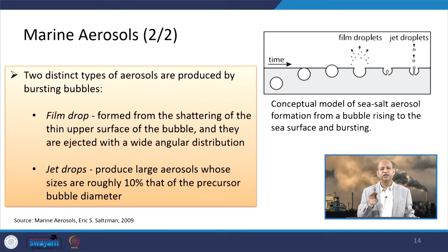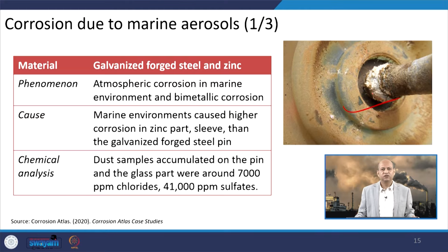As you can see, this is atmospheric corrosion in a marine environment, and bimetallic corrosion happens, you can see in the figure also. So, marine environments caused higher corrosion in the zinc part or these sleeve related parts than the galvanized forged steel pin, you can see here. So, that corrosion is because of this marine environment emitting aerosols. Okay. Then dust samples accumulated on the pin and the glass part were around 7000 ppm chloride or 41,000 ppm sulphate. So, that kind of high concentration can easily corrode whatever metal is there, unless it is a non-corrosive metal.